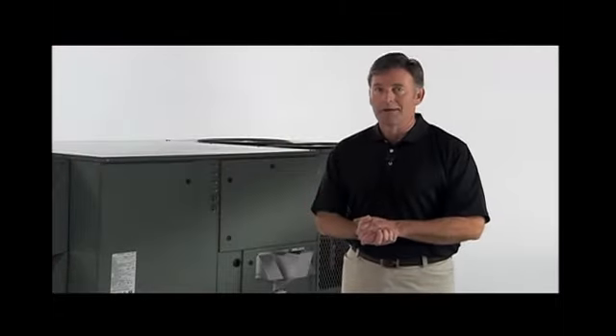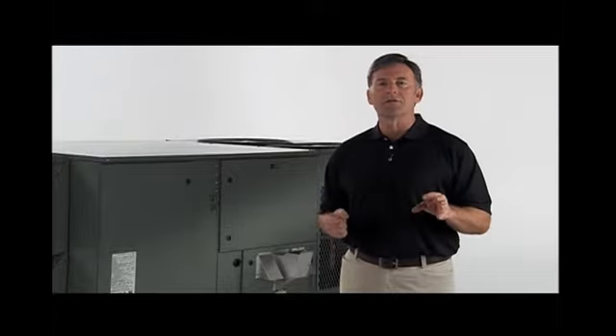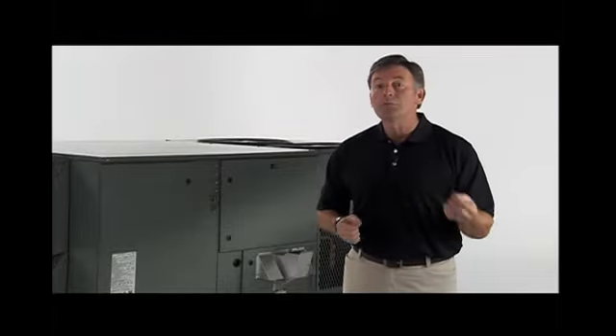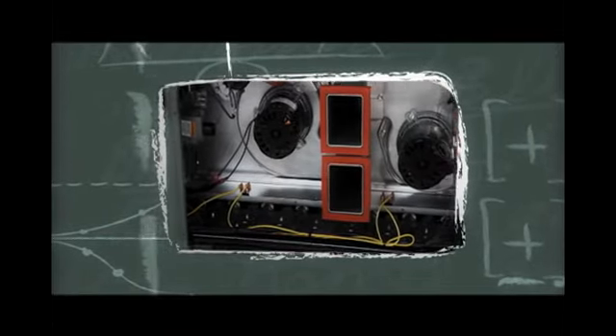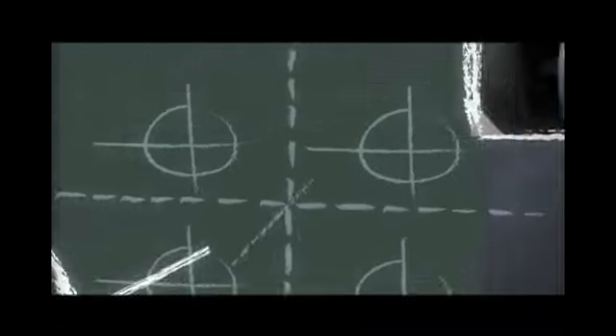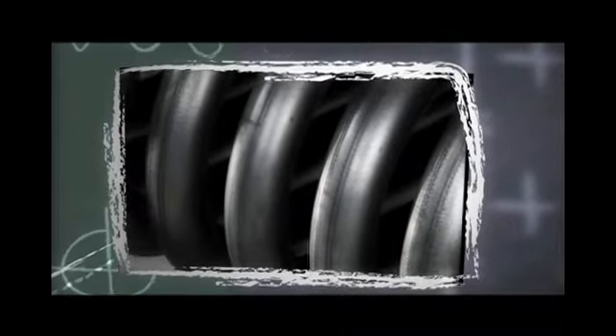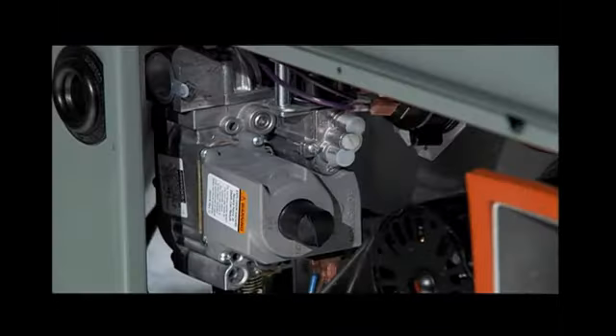Each factory-installed option is brazed into the appropriate high or low side and wired appropriately. Use of polarized plugs and Schrader fittings allow for easy field installation. Inside the blower compartment, the interlaced evaporator can also be viewed. The evaporator uses enhanced fin technology for maximum heat transfer. The TXV metering device assures even distribution of refrigerant throughout the evaporator. The single-stage 6 and 7.5 ton utilize fixed orifice metering.